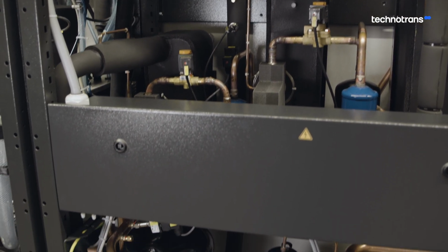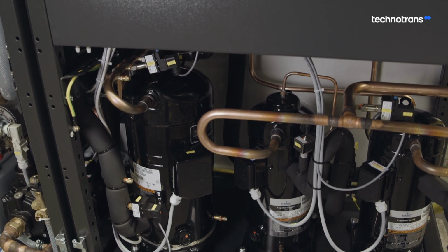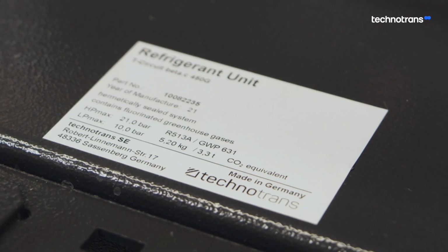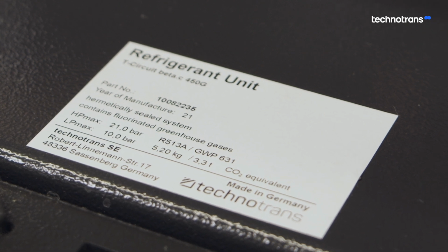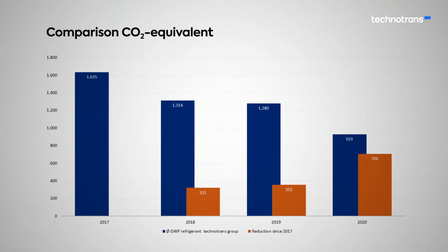First, we use climate-friendly safety refrigerants. By using R513A, we choose a non-flammable safety refrigerant. This has two main advantages. On the one hand, R513A has considerably less global warming potential. The global warming potential value of typical refrigerants such as R407C is 1774. R513A only has a value of 631, which automatically reduces the global warming potential by more than 60%.